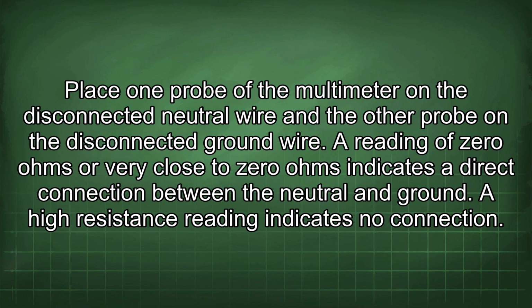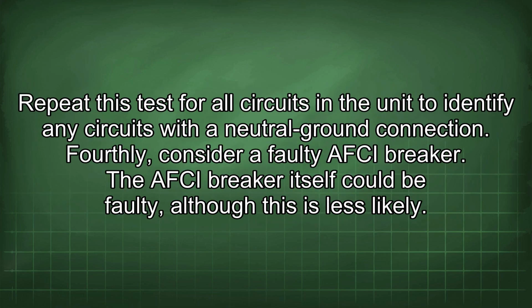A reading of 0 ohms or very close to 0 ohms indicates a direct connection between the neutral and ground. A high resistance reading indicates no connection. Repeat this test for all circuits in the unit to identify any circuits with a neutral ground connection. Fourthly, consider a faulty AFCI breaker.